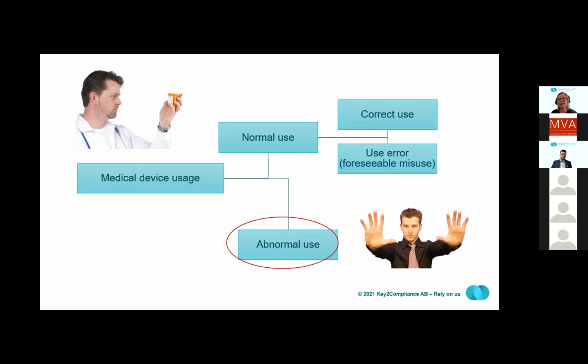So, when market feedback gives you information about any unforeseen use errors, foreseeable misuse, let's say misuse that you did not foresee in your risk analysis, then that information must be fed back into your process and assessed to see how it impacts your risk analysis, and if you need to modify your instruction for use or communication, or even the design of the device. So feedback from market will and shall be used to reassess your technical documentation and your risk analysis.